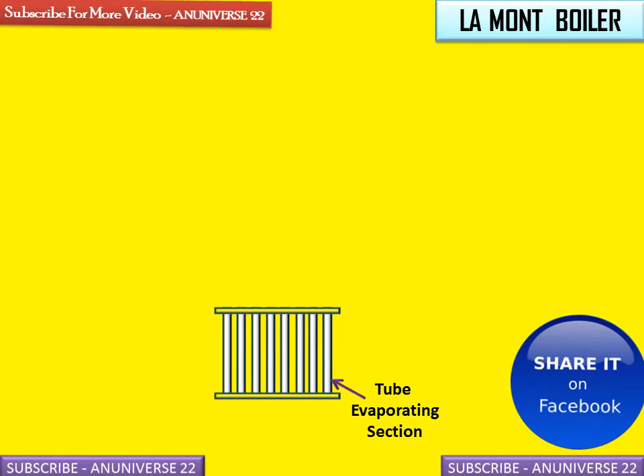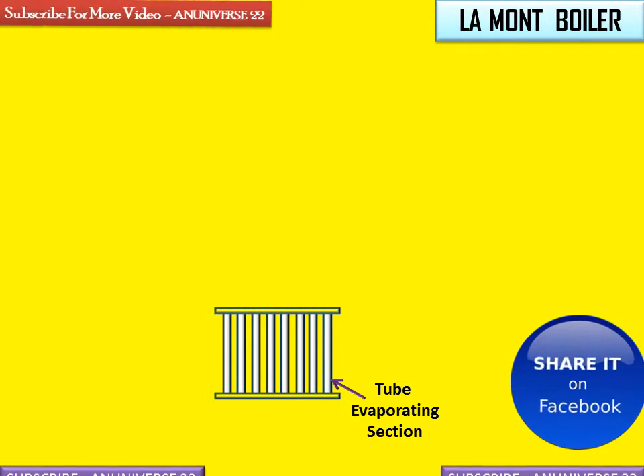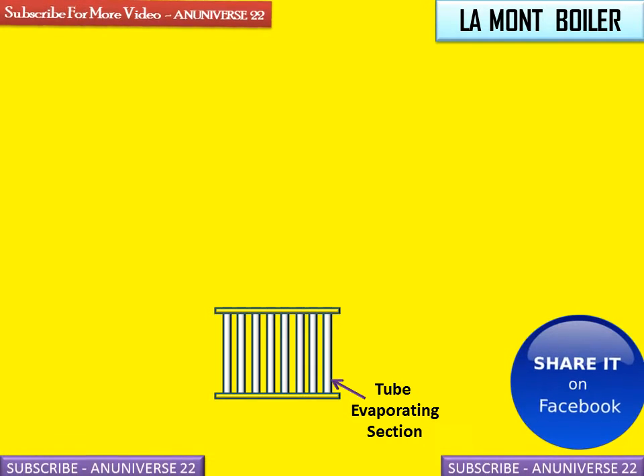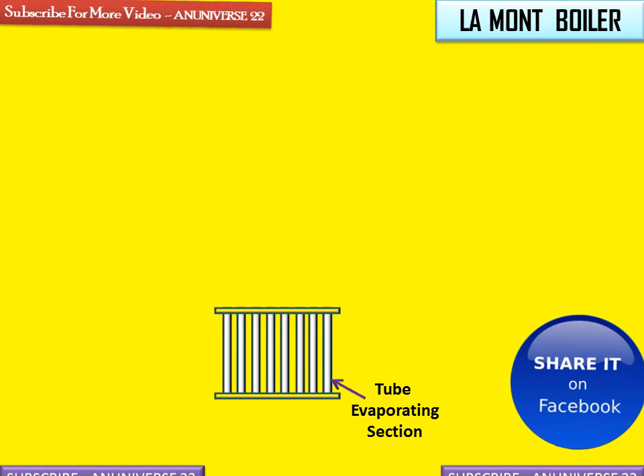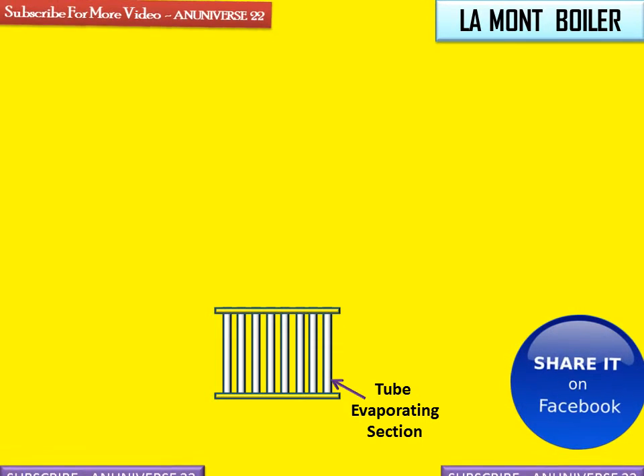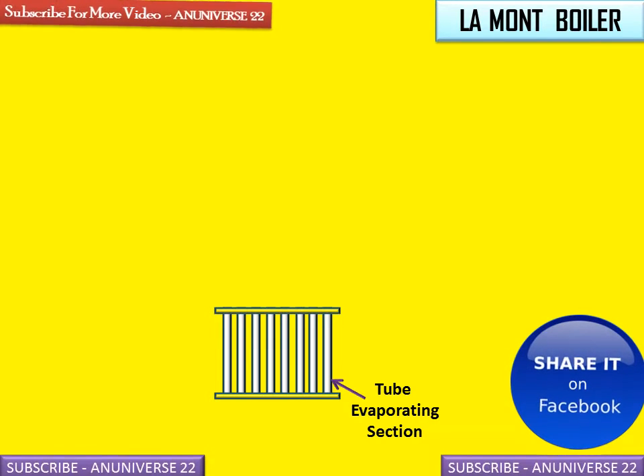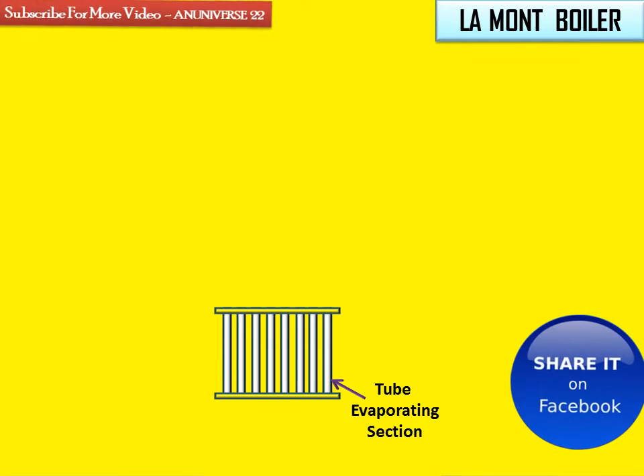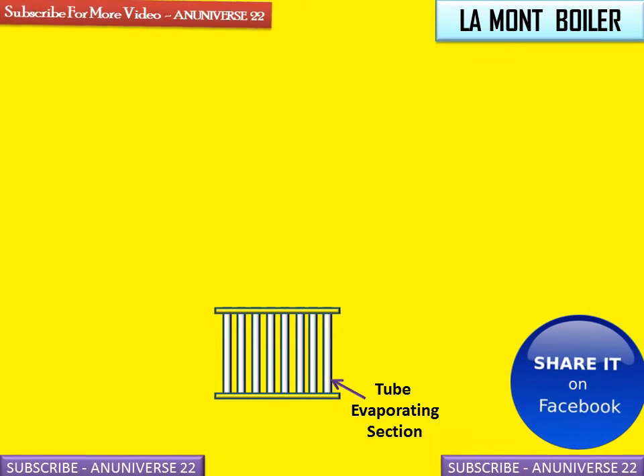Now we will discuss the main parts of the La Mont boiler. The first is the tube evaporating section. The evaporator tubes, or water tubes, are situated at the furnace wall, which increases the heating surface of the boiler. They are also positioned on the up side and down side of the furnace. The main function of these tubes is to evaporate water into steam and to cool down the furnace wall.